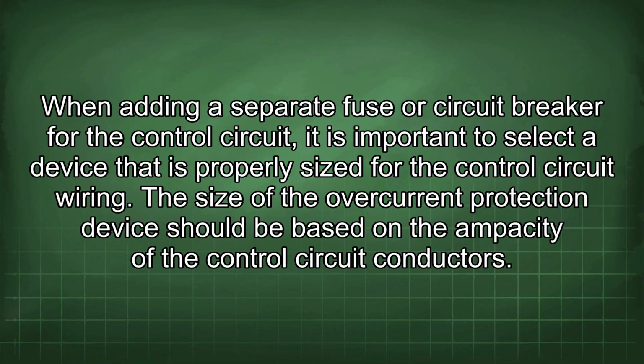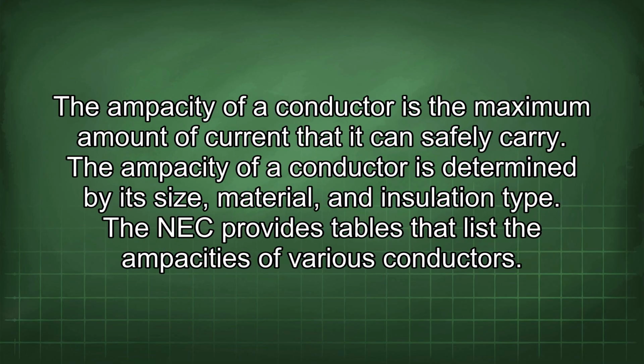When adding a separate fuse or circuit breaker for the control circuit, it is important to select a device that is properly sized for the control circuit wiring. The size of the overcurrent protection device should be based on the ampacity of the control circuit conductors. The ampacity of a conductor is the maximum amount of current that it can safely carry. The ampacity of a conductor is determined by its size, material, and insulation type. The NEC provides tables that list the ampacities of various conductors.